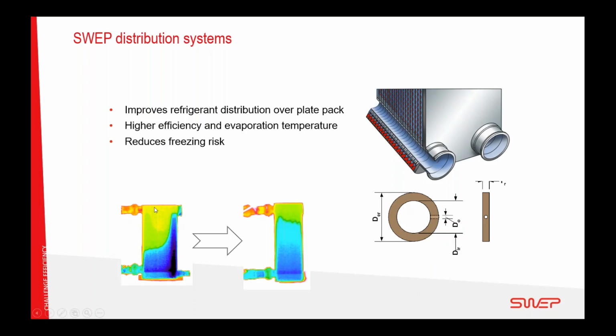And in this case, only 50% of the heat exchanger that you paid for is actually doing what you want it to do. And 50% is just a gas heater, not efficient. A good functioning distribution system makes sure that the gas is not allowed to take the shortcut, but is equally distributed together with the liquid, so that as much as possible, or 70%, of the heat exchanger that you paid for is really evaporating.